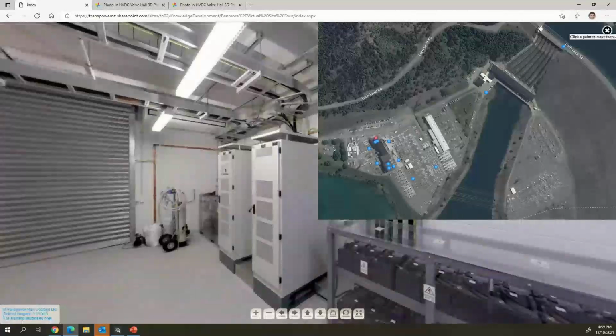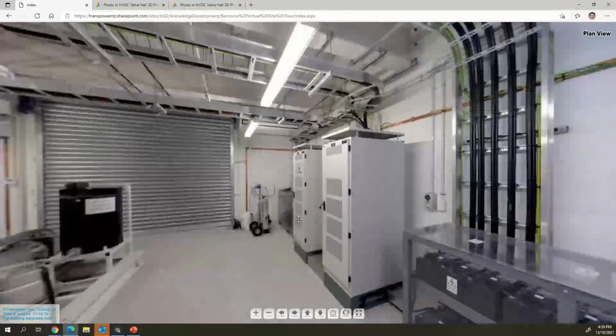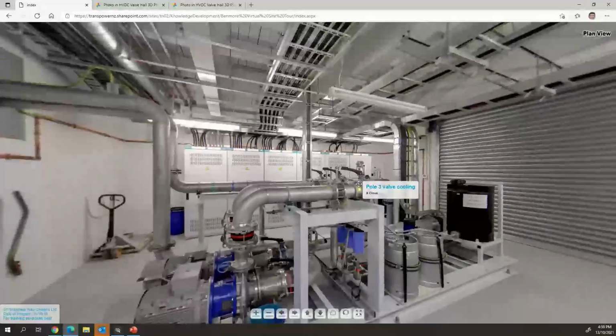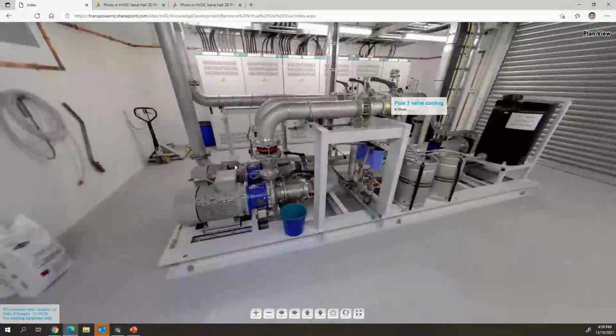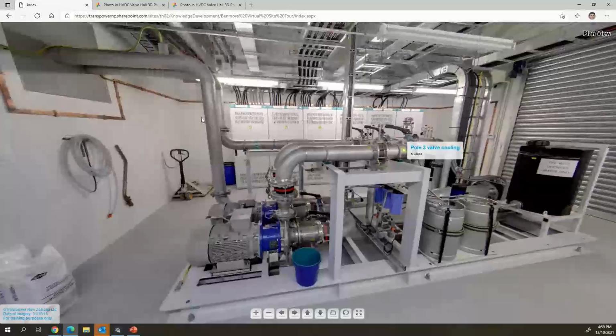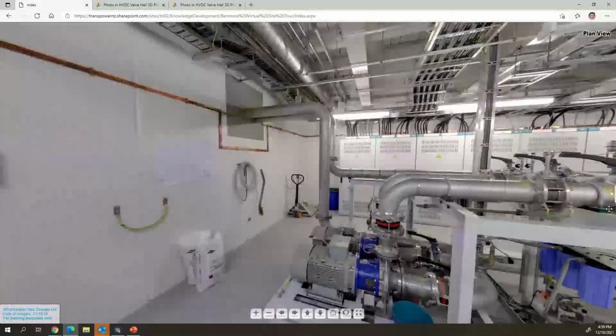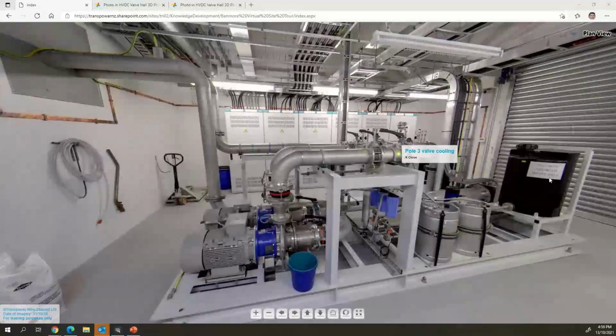This is the valve cooling for pole 3. So you can see our 2 pumps here, duty and standby. So you only ever have one running, and if there's a fault with it, it'll swap over to the other one. You can see the pipes going into the valve hall there. There's water in, water out, and then it goes under the floor to go to the coolers out the back. So I'll show you the coolers when we go to the DC side.